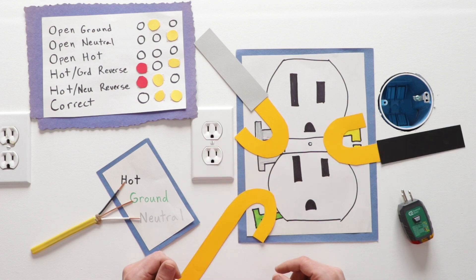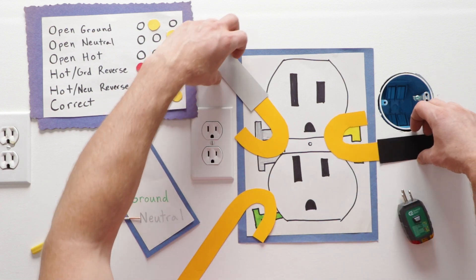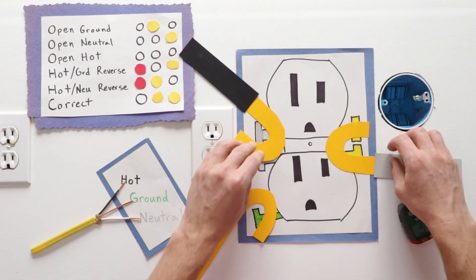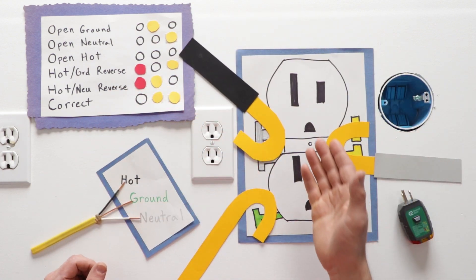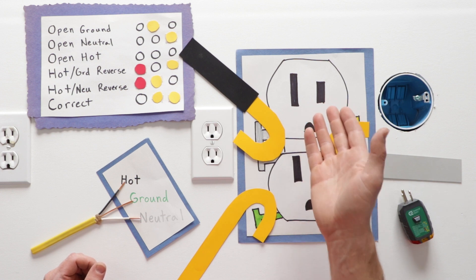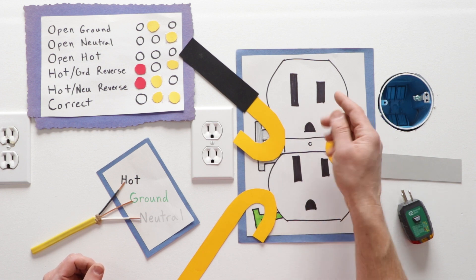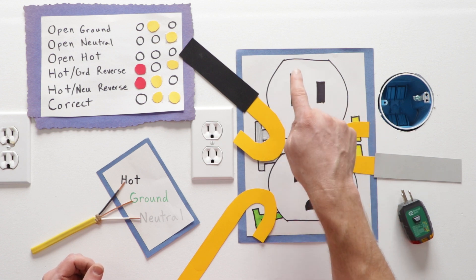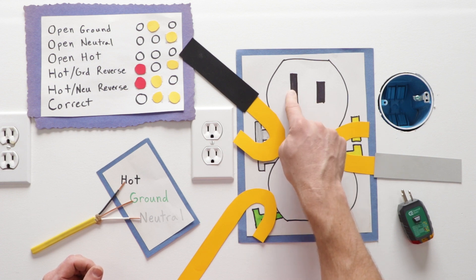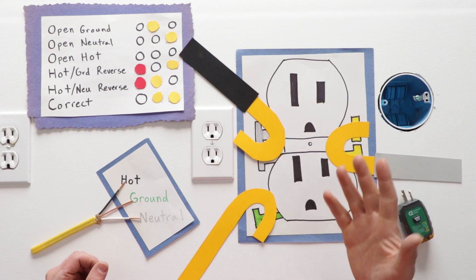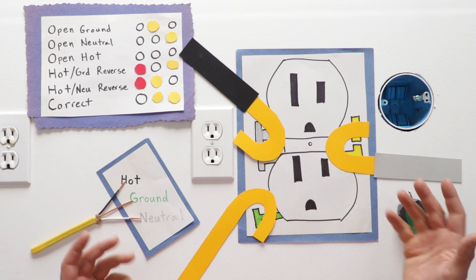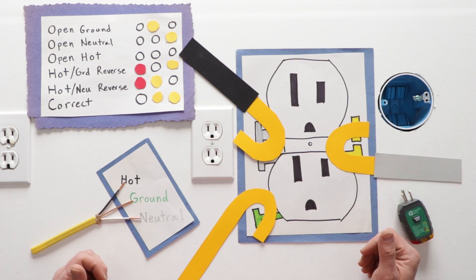The next situation is your hot and your neutral reversed. There's also a really bad situation because you may have an electric appliance and it's expecting the hot to come out of this small prong slot, but it comes out of this big prong slot and it's running reverse through your electronics, which could break something or start a fire.